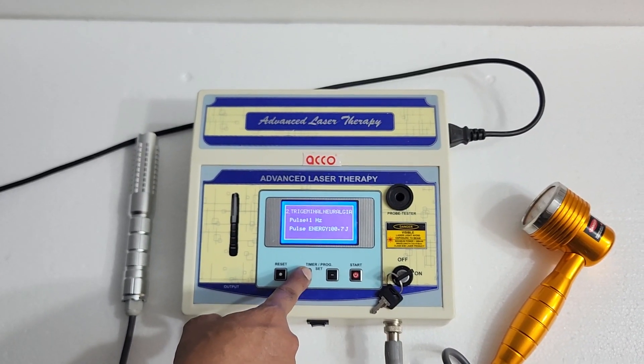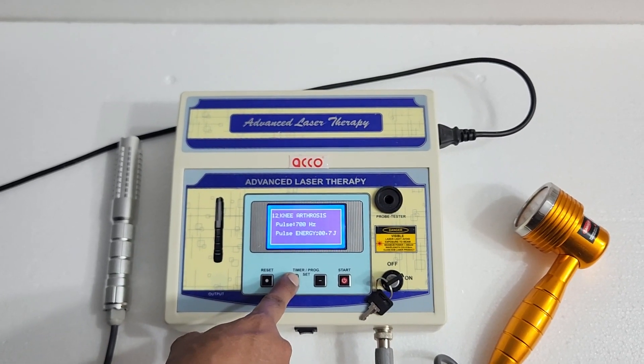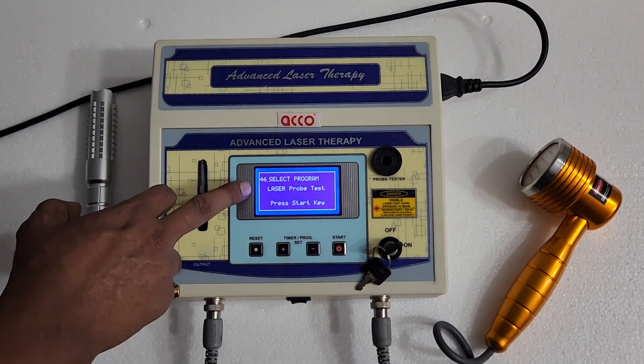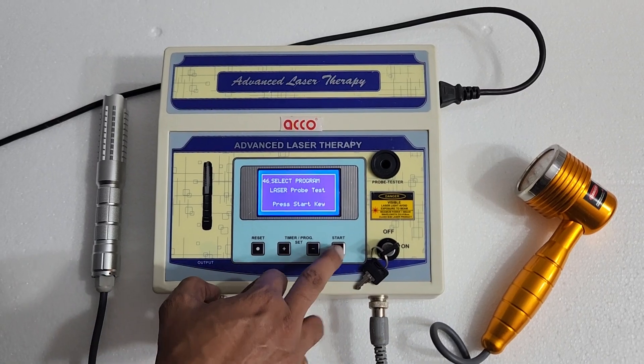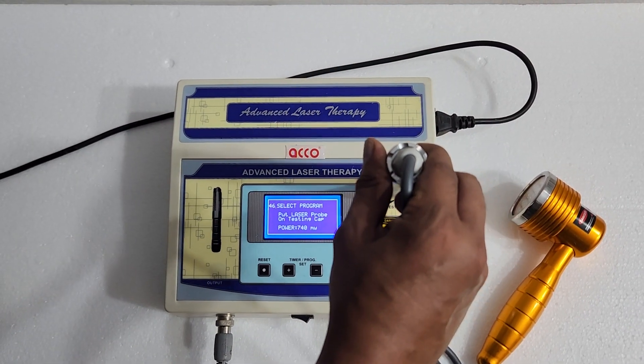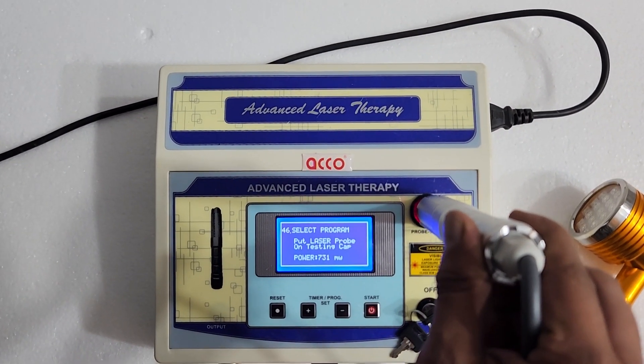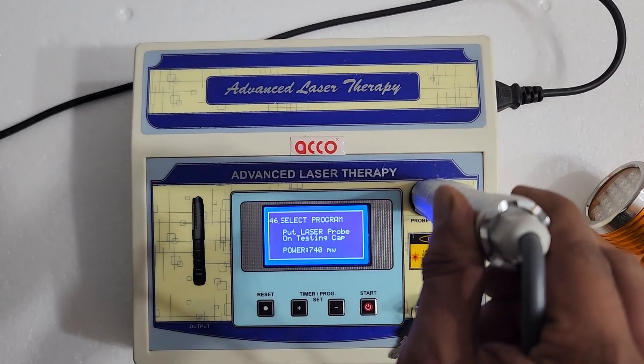You can go to the 46th program to test the probe. In this program you can test the probe power. Press start, select the probe, and just put it inside. You can see the power — it is 738, 740.